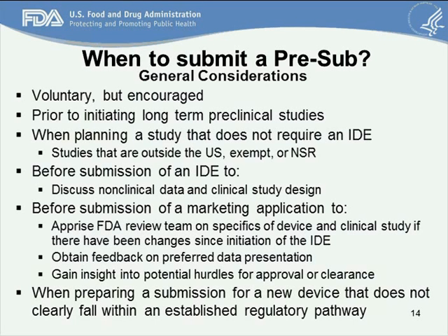We recommend pre-submissions before submission of an IDE to discuss any non-clinical data or clinical study design issues. We think that having this interaction before the IDE could lead to more successful IDE outcomes. We recommend pre-submissions before submission of any marketing application to apprise the team on specifics of the device and clinical study if there have been changes since the initiation of an IDE.